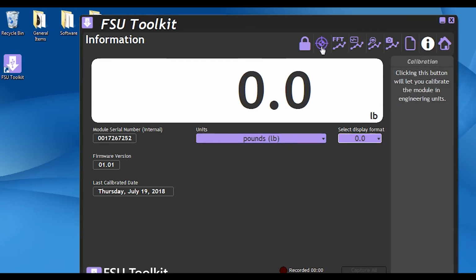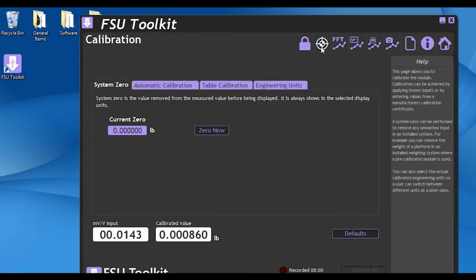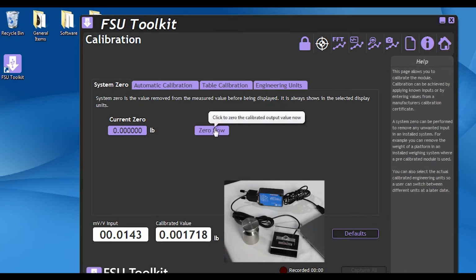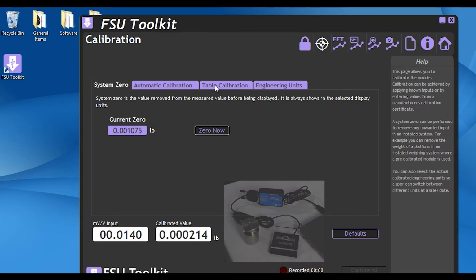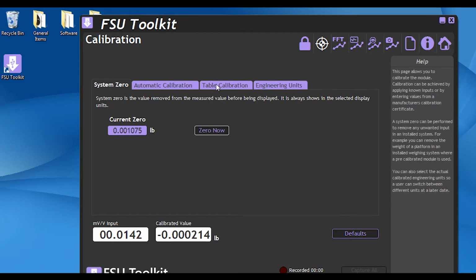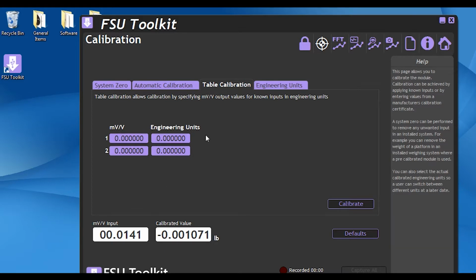Now we're going to click the target, which is the calibration icon. Make sure the scale is unloaded, and then hit 0 now. Make sure that it's zeroed. And now go to the tab that says Table Calibration. As you can see, when we do the table calibration, there are 4 potential entries. The first point we're going to take is going to be 0. So we really won't have to enter any information in here as long as it's 0 millivolt per volt and 0 pounds. That is the engineering unit pounds that we selected.